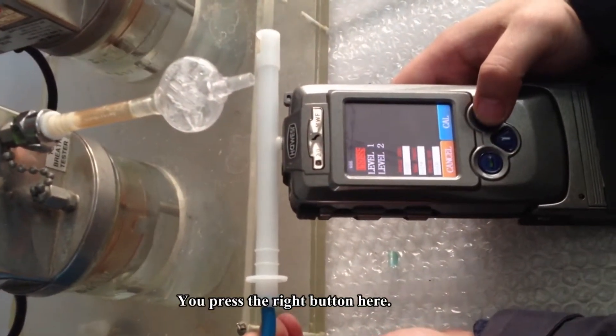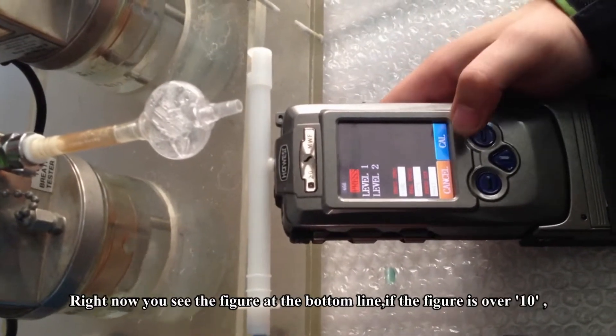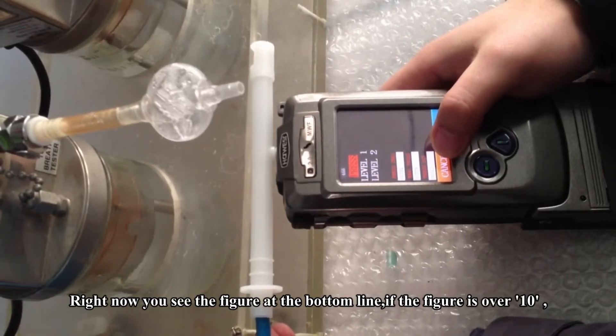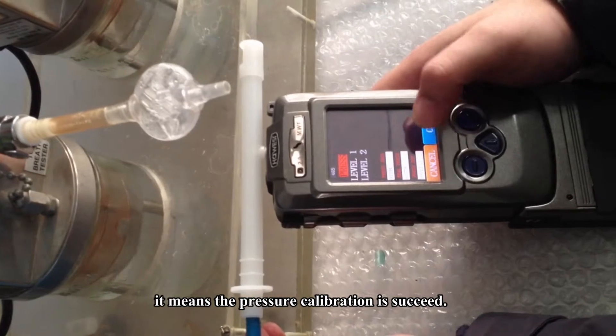Pump on the air ring, then press the right button here. Right now you can see the figure at the bottom line. If the figure is over 10, it means the pressure calibration is successful.